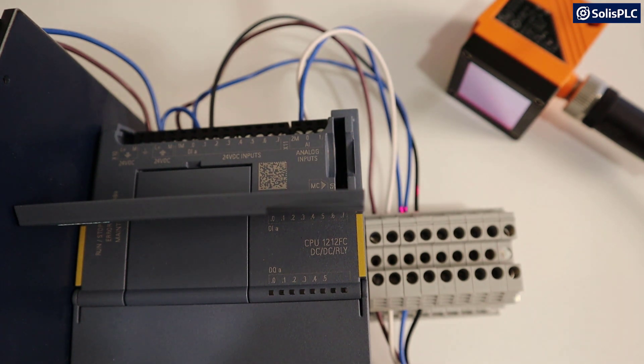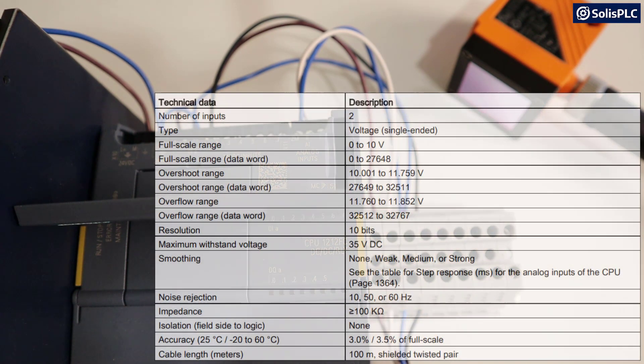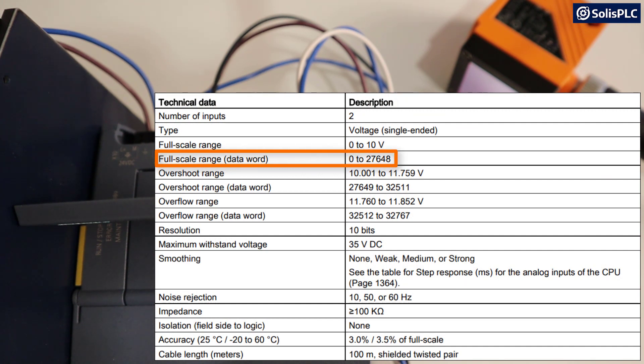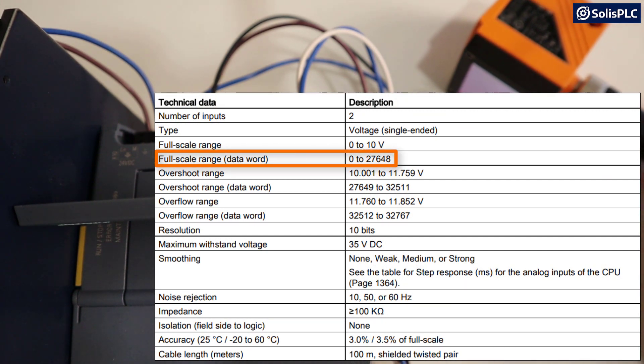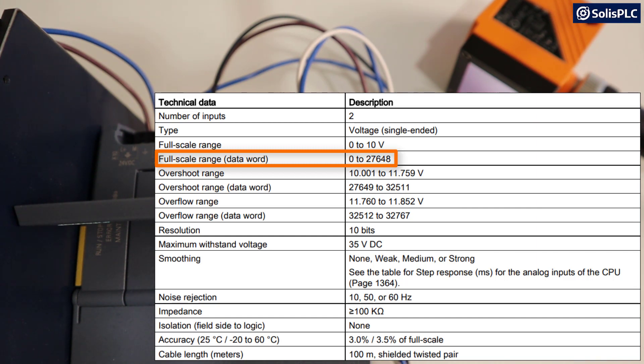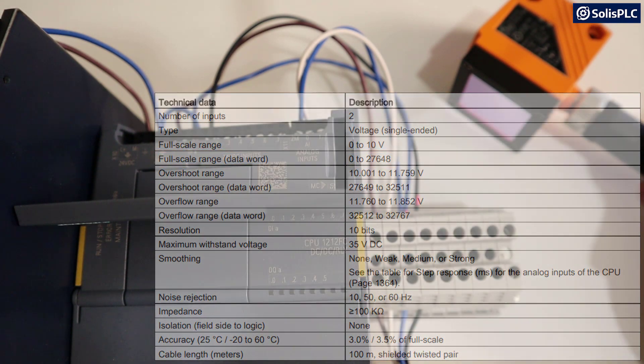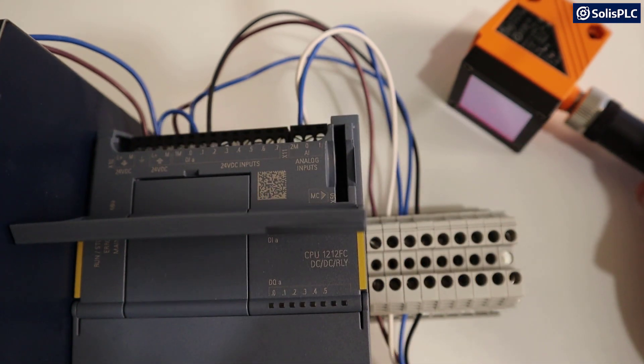Now, what's also important to note if we go into the data sheet is that the full scale range, meaning the engineering conversion value that this voltage is going to drive is going to provide us with a data word of 0 to 27,648. And that's going to be the value that we'll need to scale in our software.